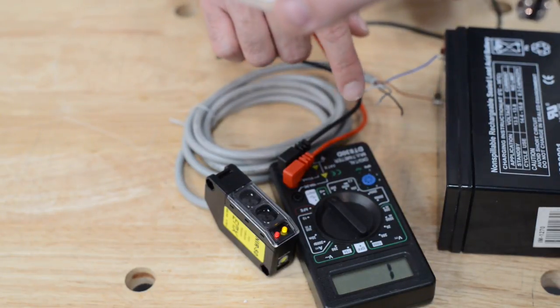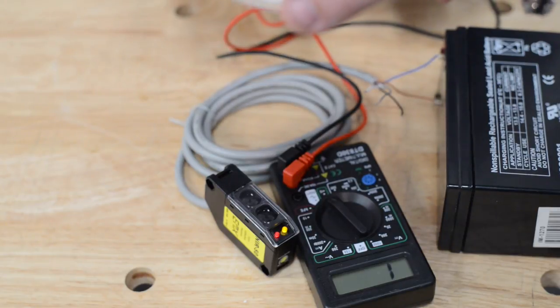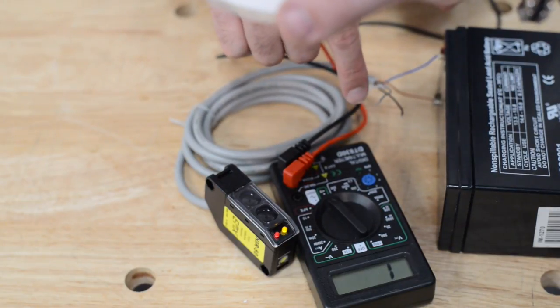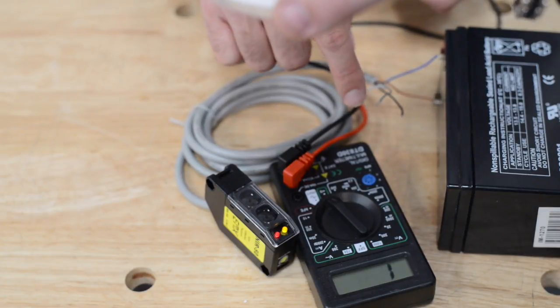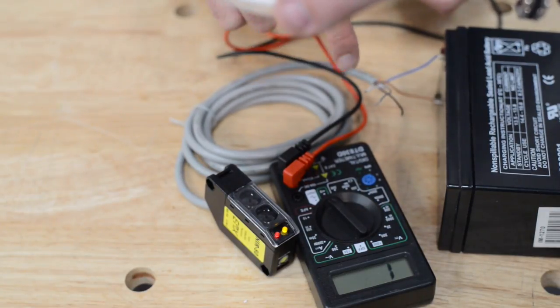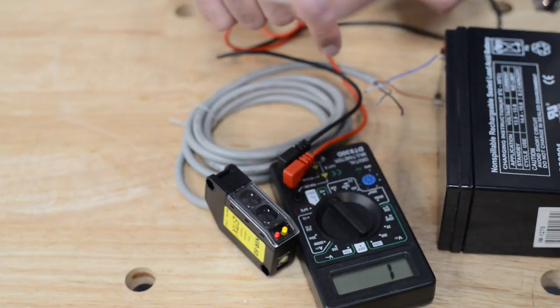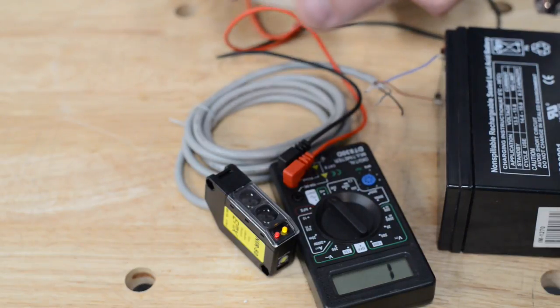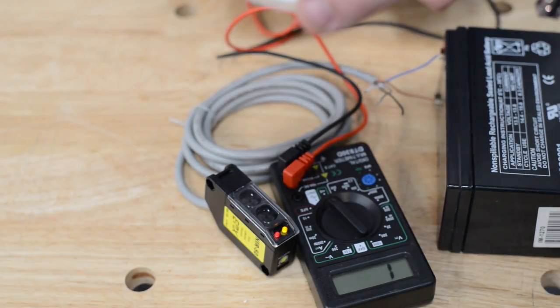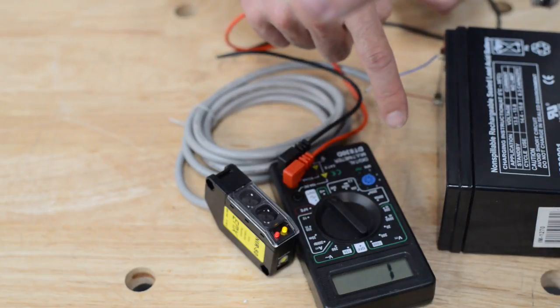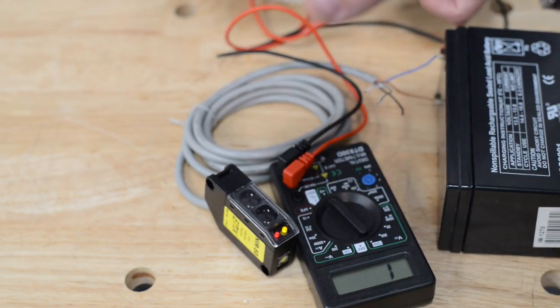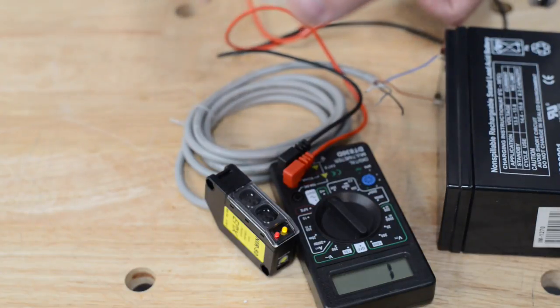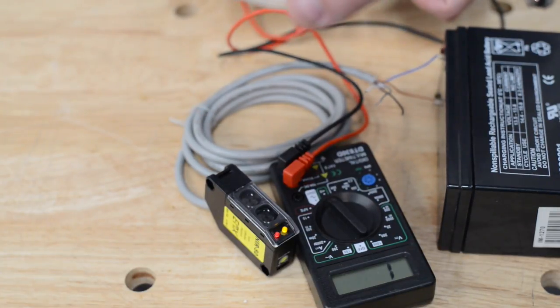I tested between the white and the black and I did have a connection. So since I'm expecting common to be connected to normally closed, that was there. So I know that the black is my normally closed and the white is my common. And just for demonstration purpose, I tried the black to the gray and there was not continuity there even though there was a connection here. So the gray has to be my normally open.